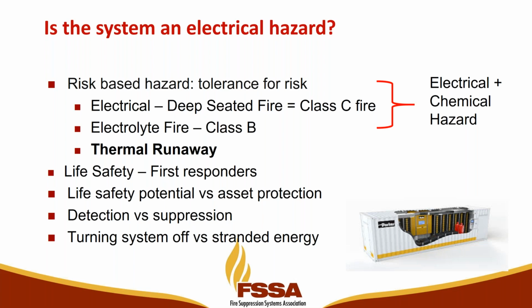But we want to take into account life safety and first responders. Are we taking care of assets? Are we taking care of life safety? What are we looking at when it comes to detection and suppression systems? With a lot of the electrical work we deal with, you flip the switch and it's dead. With batteries, that's not the case - we have what's referred to as stranded energy. So you can flip the switch, turn the whole system off, but we've got the same amount of energy that still exists inside that enclosure. Especially in a fire condition, that energy doesn't go away.